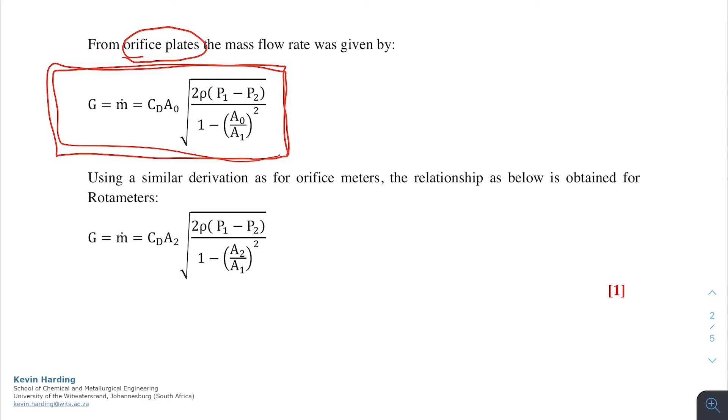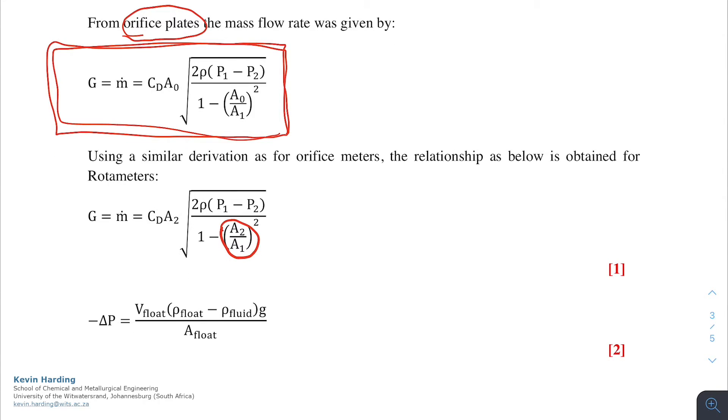Using this equation and substituting the values for A2 and A1 for the area as we have in the rotameter, we are left with equation 1. We can then replace P1 minus P2 with delta P, which we define as the volume of the float multiplied by the density difference of the float and the fluid, multiplied by g, divided by the area of the float.